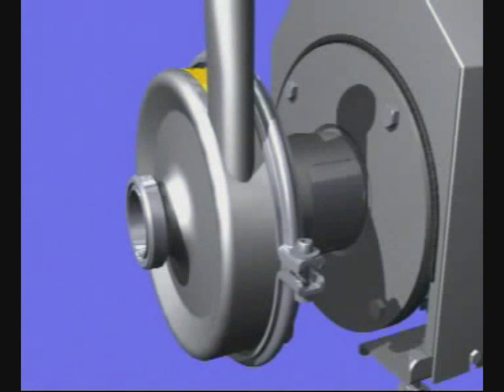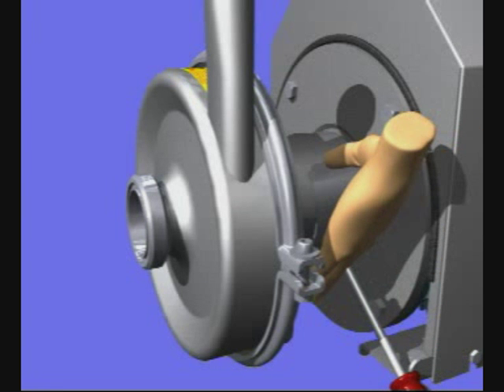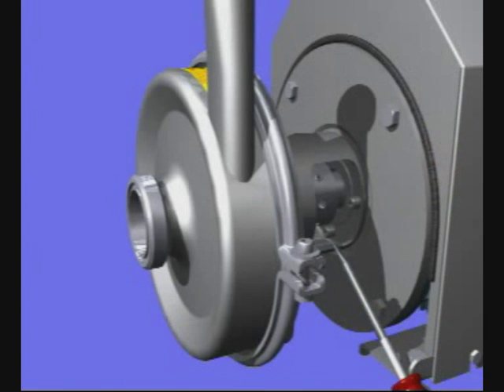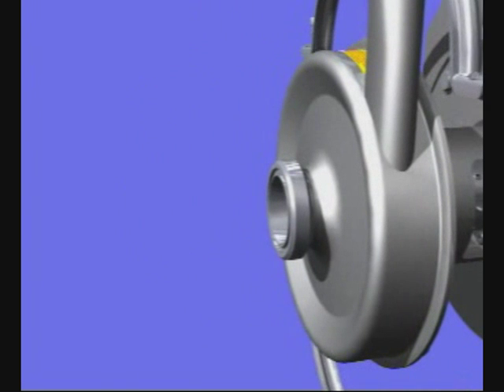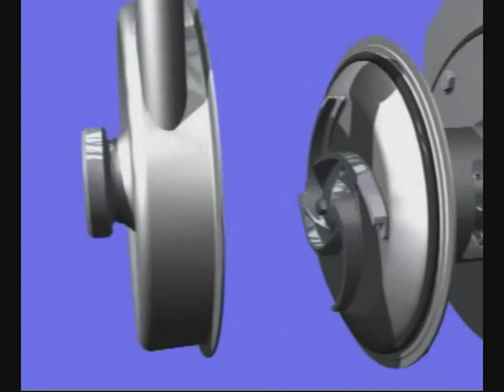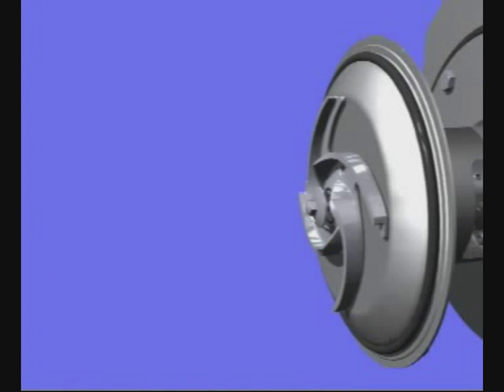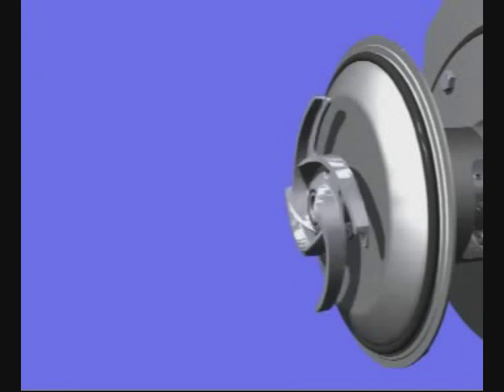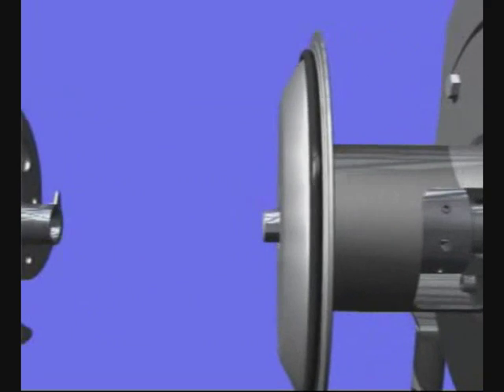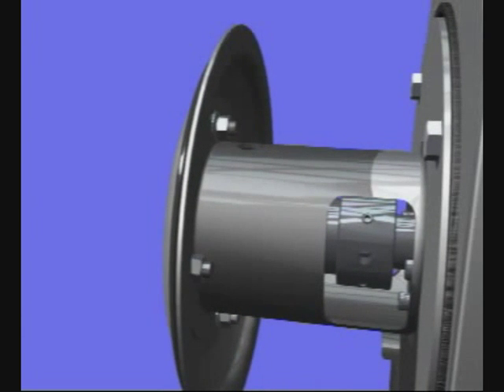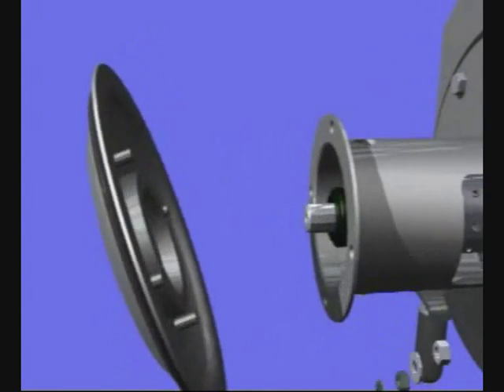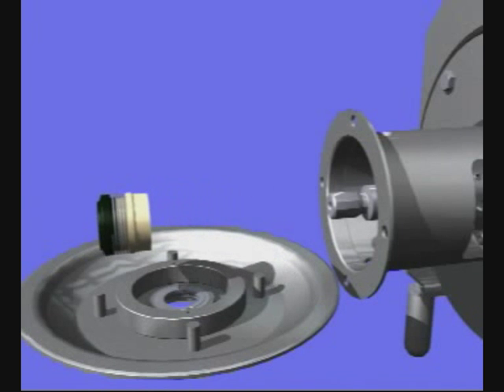You can easily convert the SiC shaft seal from single to flushed. Dismantle the pump as shown in the previous sequence. When rebuilding the shaft seal, you must first remove the back plate. Loosen the nuts to remove the back plate and rotating shaft seal.